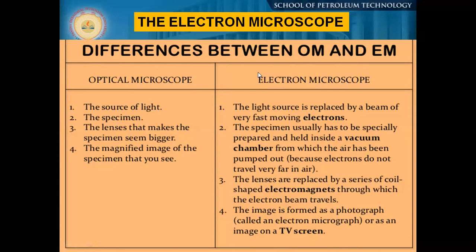In the case of the normal microscope, we have the light source only, whereas in the electron microscope, it is a beam of electrons — a beam of very fast-moving electrons. The specimens have to be specifically prepared and held inside a vacuum chamber from which the air has been pumped out. The lenses are replaced by a series of coil-shaped electromagnets through which the electron beam travels, and we try to converge the beam so that we have a specific probe current, which is not present in the normal optical microscope.